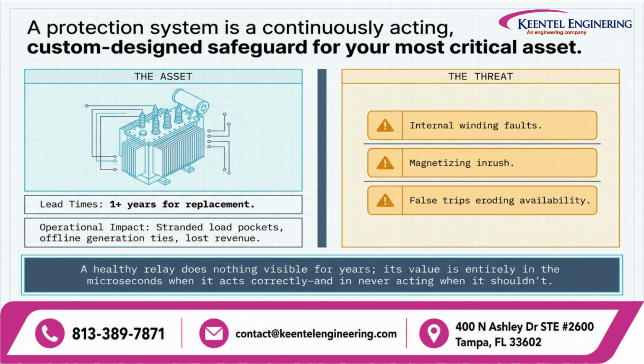Consider the transformer itself. Replacing a major transformer can involve a lead time of more than 1 year. During that period, the impact can extend far beyond the transformer itself, creating stranded load pockets, offline generation ties, operational restrictions, and significant lost revenue. At the same time, the protection system must deal with several very different threats. The first is an internal winding fault. This is a genuine electrical fault inside the transformer and requires extremely fast detection and isolation.